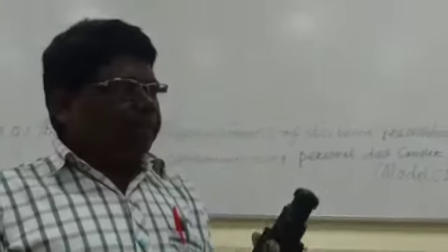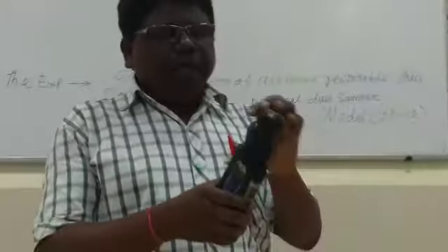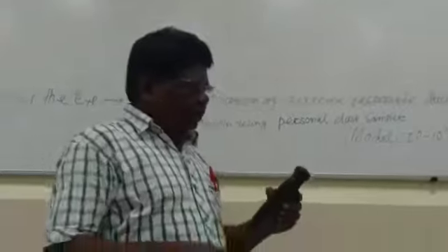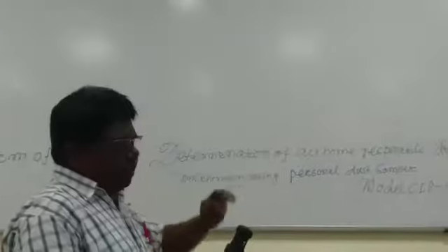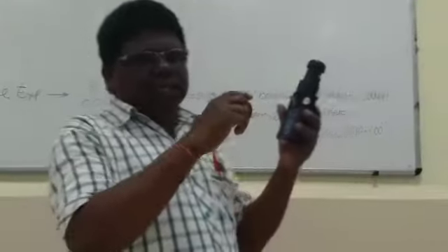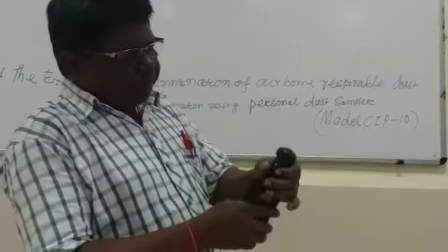After taking out the sample, you have to remove the protecting cap and take the final weight in an electronic balance. Similarly, as you studied earlier with the GDS, in the same way you calculate the dust concentration. What is the dust deposited inside this filter, I mean this rotating cap?